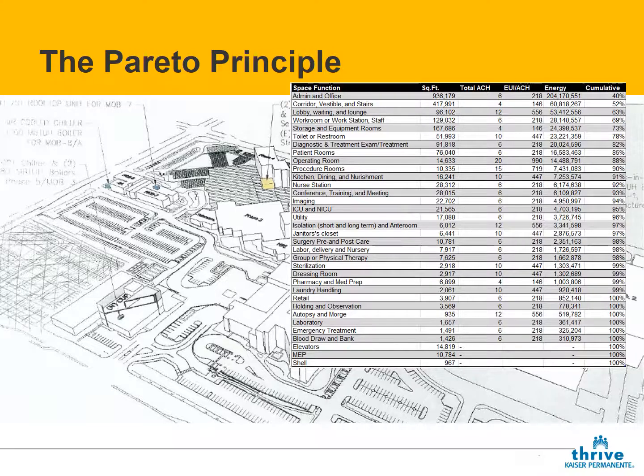Patient rooms have come down from 6 air changes to 4 air changes. Corridors are down to 2 air changes. So there are big opportunities that come with every code cycle, and the ASHRAE thing is the same. There are reductions going on with the different versions.